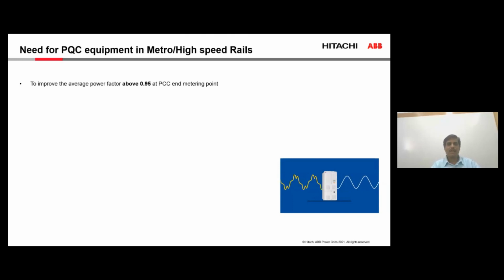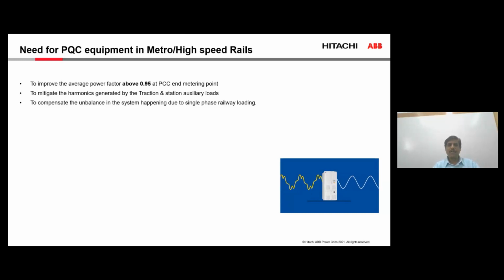Now, when we look at the power factor, which is the ratio of active power to the apparent power, the objective of the power quality equipment is to take the power factor to at least 0.95 at the metering point. Then we also need to look at the harmonics generated, which need to be rectified and eliminated, and also we look at unbalance that is happening in the traction system. We have to correct the unbalance. These are the things that power quality equipment needs to accomplish.